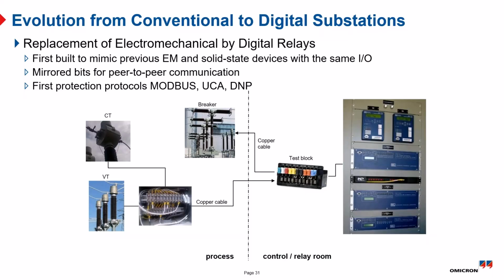So here's a traditional substation where I have CTs and PTs and copper cable going in through a test block and going to my individual relays. If I'm going to test this, I open up my test block, I plug in a test paddle. This is where I'm going to inject my test set voltages and currents back into my relay and verify the relay's response. So relays, binary inputs and outputs also go back through a test block. And I can provide a stimulus through the test block to the relay and measure the relay's response through the test block. Pretty simple, right? Too bad it's all going away.